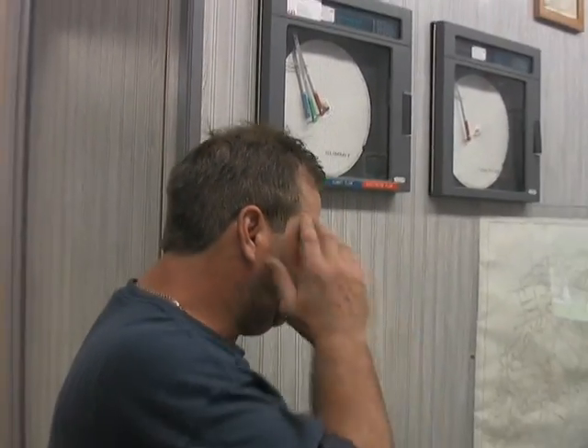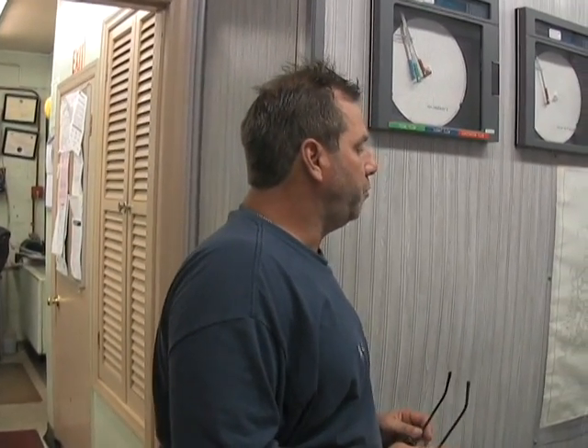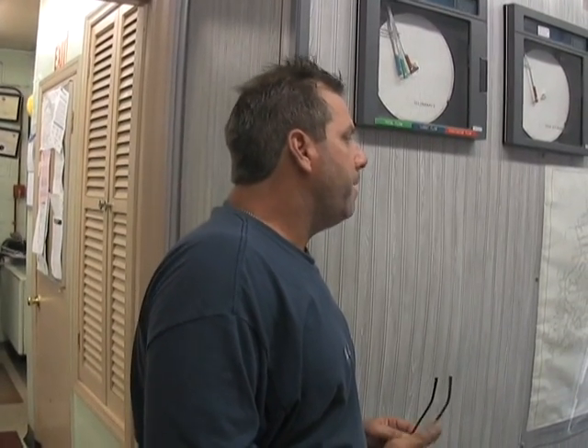Well, we were talking about lining, and the borough has spent a lot of money. And when you read the report, all that infiltration gets in through the sewer system, being that we have 85% vitrified clay pipe. On a normal day, if the ground is a little bit wet, we're doing on an average day 1.5 million through the treatment plant. If we get 1.5 to 2 inches of rain, that flows up to 4 or 5 million. 3 inches will take us over to 6. The plant can do 3 million gallons.